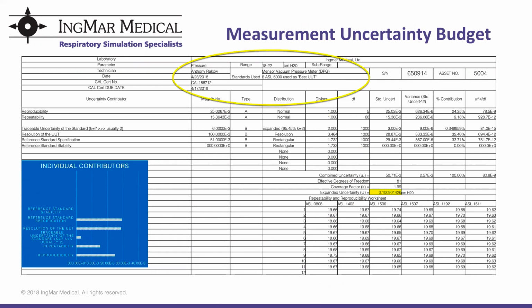Here's what a measurement uncertainty budget looks like. Here is a measurement uncertainty budget for our vacuum pressure meter, where we are testing 20 centimeters of water. Here are the ingredients we use to make up the measurement uncertainty budget, shown here as contributors. Here's us recording the test results of 6 ASL 5000s running the same test 11 times on each ASL. As you can see, we use a wide range of ASL 5000s, ranging from older to newer, to give us a broader scope of the measurement. So after we enter all those factors, the ingredients, we have a statistical figure of the doubt represented as expanded uncertainty that equals 0.1 centimeters of water for our measurement of 20 centimeters of water.